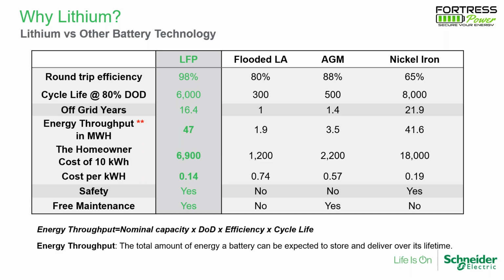Regarding safety, lithium phosphate is very, very safe. We don't have any issue, and you don't have to go back for maintenance. With flooded lead acid, if you don't do the maintenance, you have a good chance of shorting the batteries. And maintenance is another big factor. In a traditional system, you need a ventilation system, and you have to have people go back and do maintenance on the battery stack, which with lithium batteries you don't need. Next slide, please.